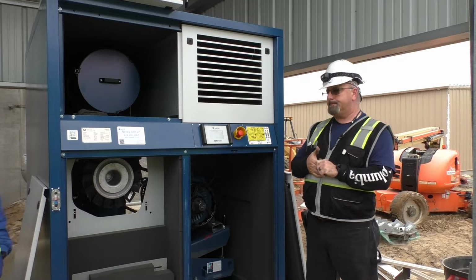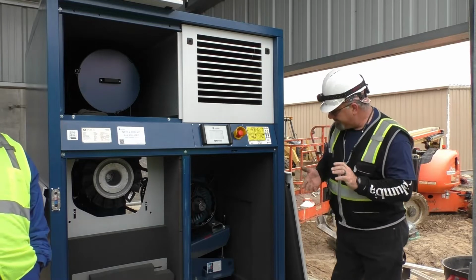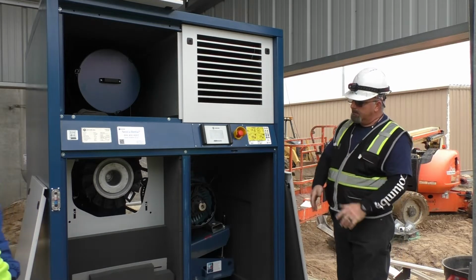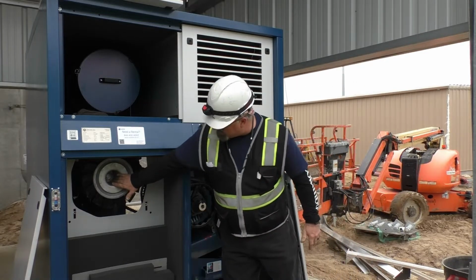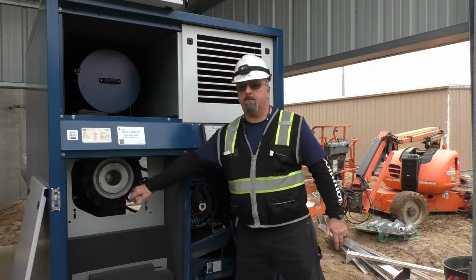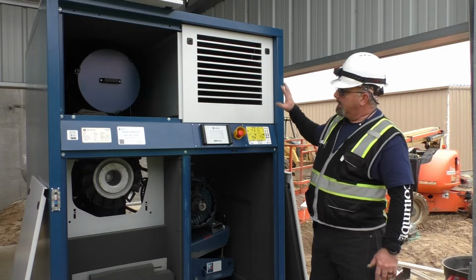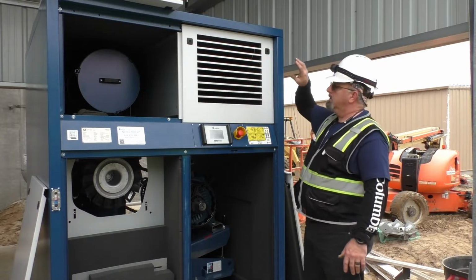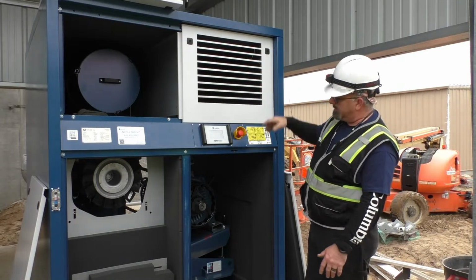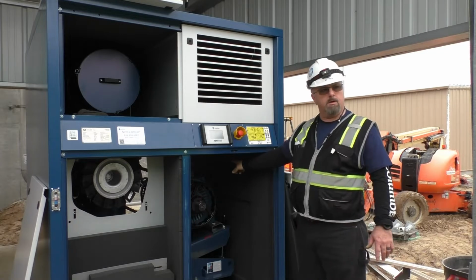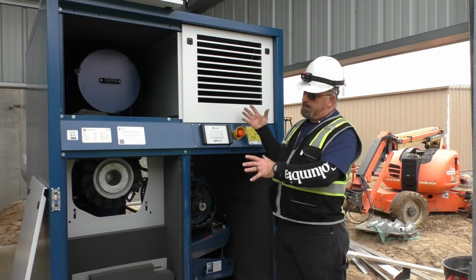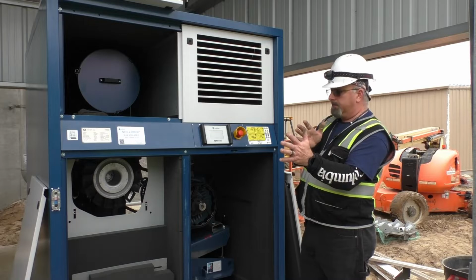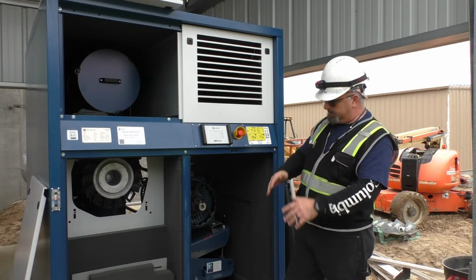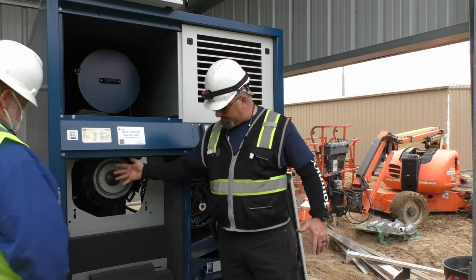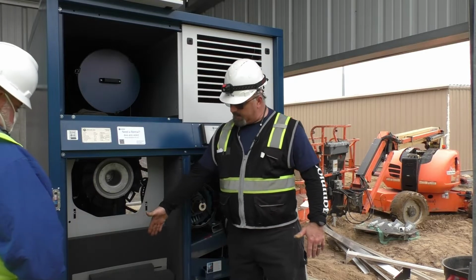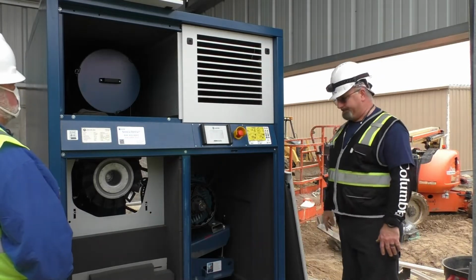All right, so the next item that we're going to cover, over here you have your attached fan. This is attached to the end of the input shaft. It pulls air in here. It goes to the back of the cabinet. There's an attached fan on the back of the motor. So both of those pull air toward the front of the enclosure. This fan pushes it out here. It goes down and it exits the back of the machine.